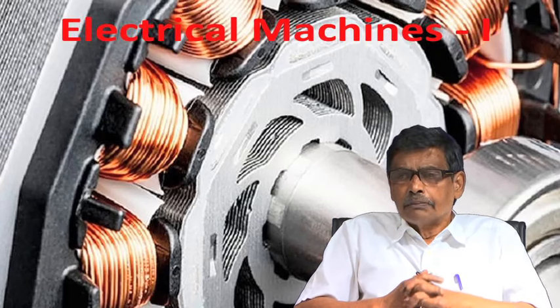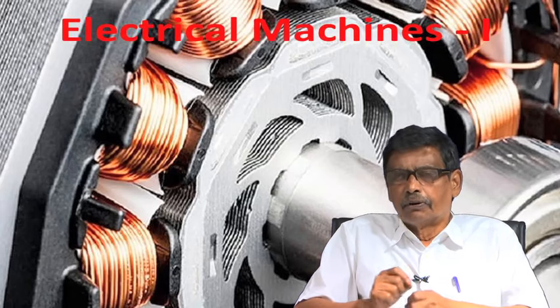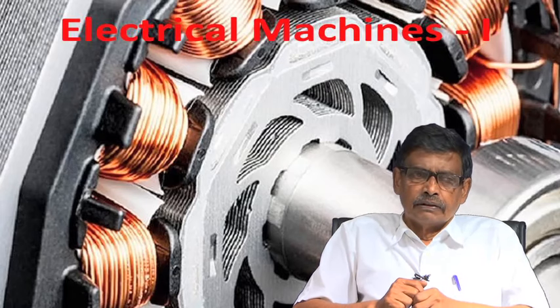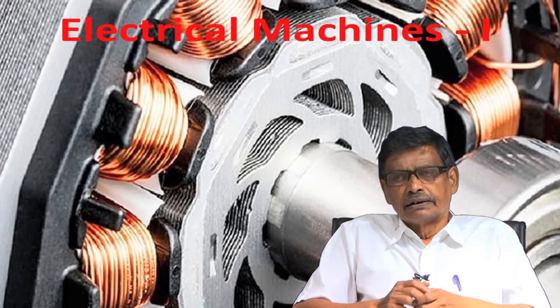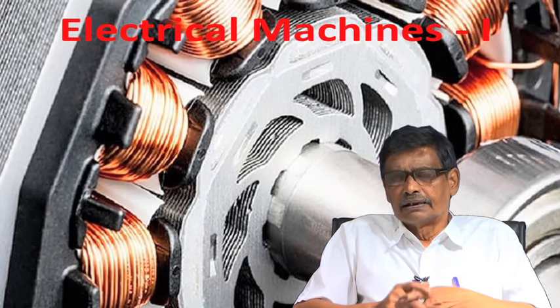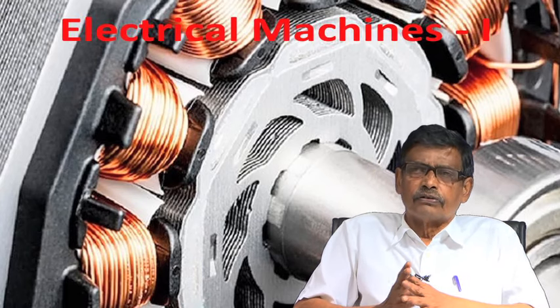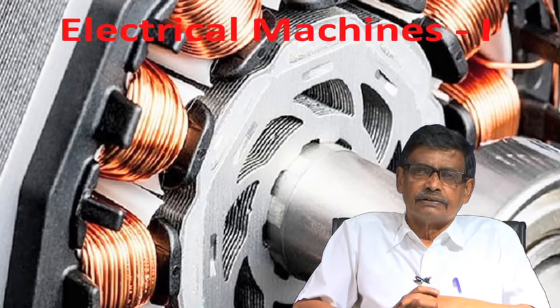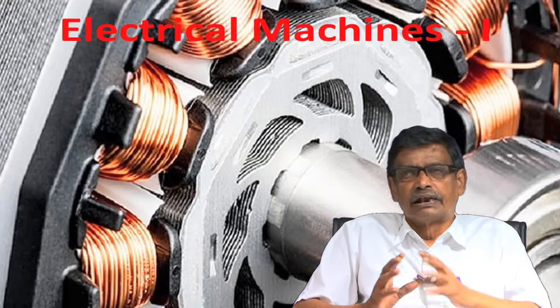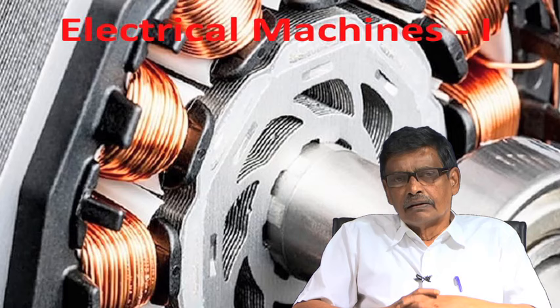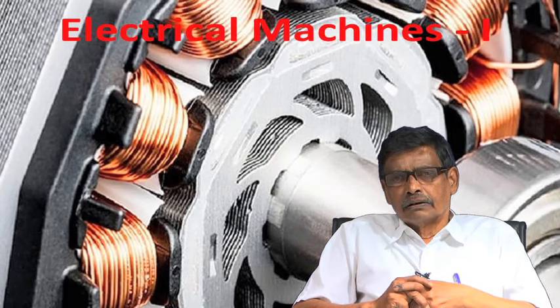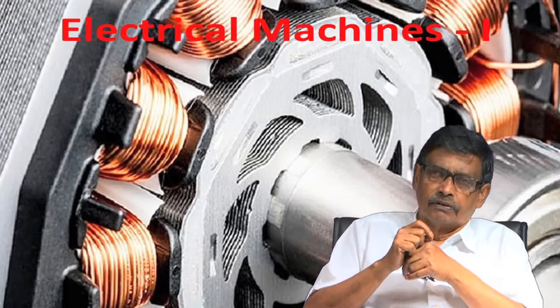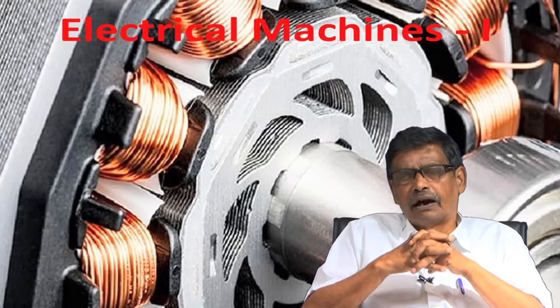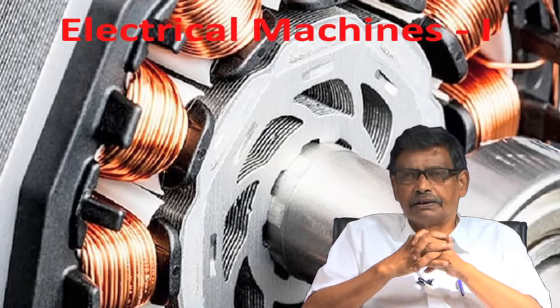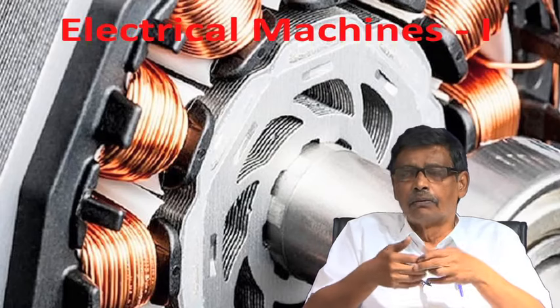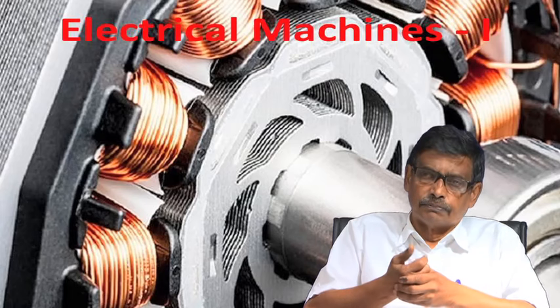Armature reaction, for example, is an important topic in DC machines. When the armature carries current, it will also create flux, and as I told you, any flux component along the brush axis creates a problem. That is called the commutation problem. The ill effects of armature reaction, and how to nullify them in a DC machine, I will also discuss. You can use the compensating winding or interpoles.